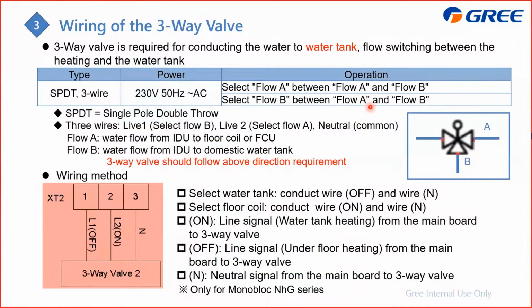Especially for the monoblock, you need to install the three-way valve. For the split type and the all-in-one, it is already integrated, so there is no need to install it. For this one, you need to use this. First, select which direction is for the water tank and which direction is for the FCU or the floor coils. And you need to follow this requirement in the actual installation: flow A is for the floor coil and FCU, and flow B, which is from here, is for the domestic water.